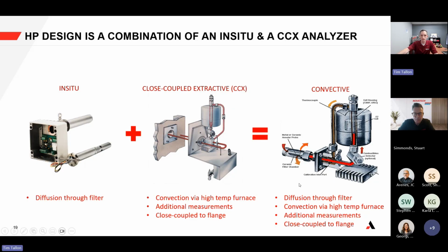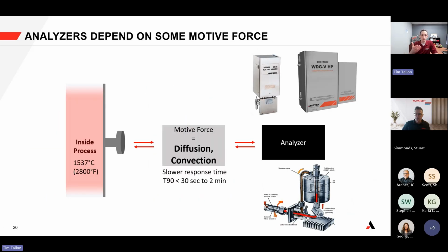So the advantage is also added measurements, like you can see in combustible measurement here, and also having it on the process flange. So putting it all together for an HP analyzer, specifically the HP II analyzer, WDG-V HP analyzer, it's diffusion and convection that enables a faster response relative to an in situ, but also the ability to endure high particulate environments with added measurements with easier serviceability. So I hope that answered your question.